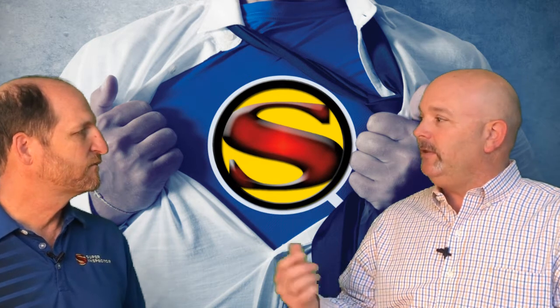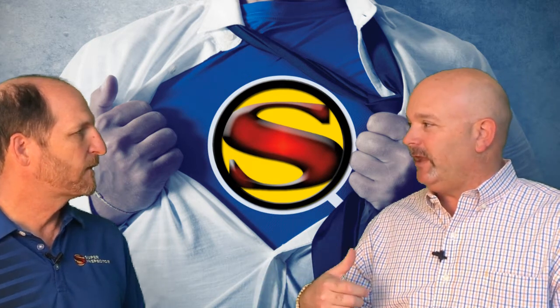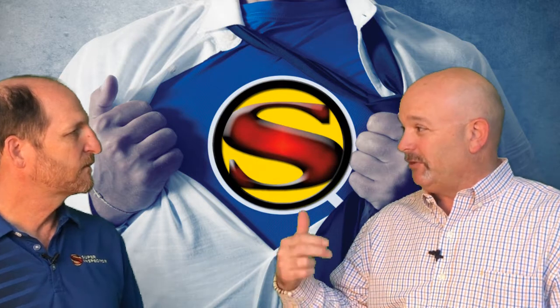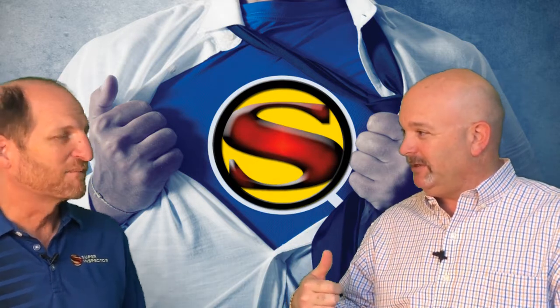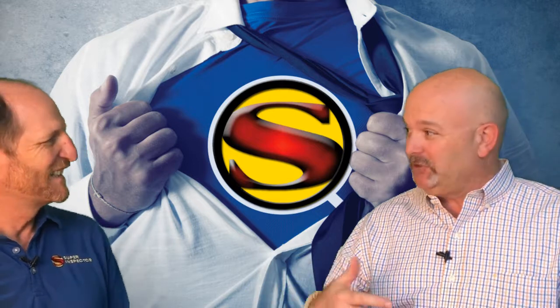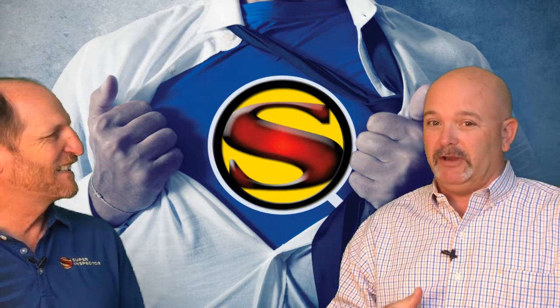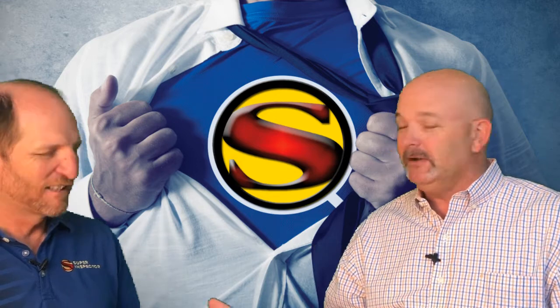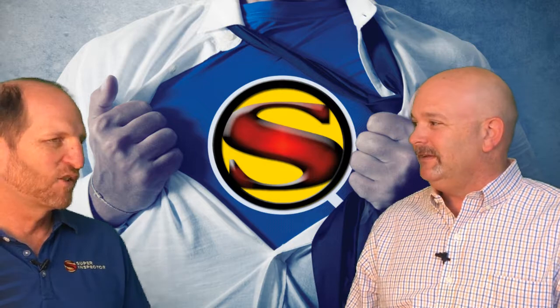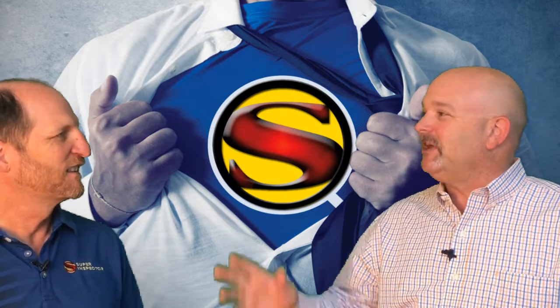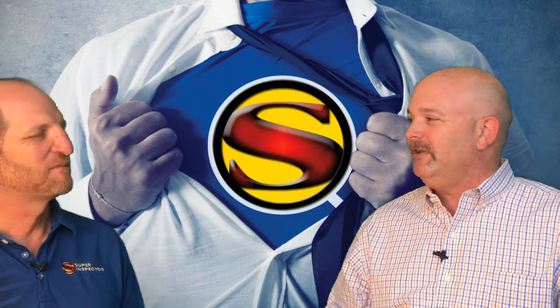And let's talk about the secondary pipe going outside. If we see water dripping from that as the unit's running, it's supposed to go that way, and that's your secondary, which you want because you don't want it going back in the house somewhere. Right. But that's not common. That's not normal. It's not normal, right? It's common for it to do it if it's secondary, but it's not normal. You know that there's an issue.